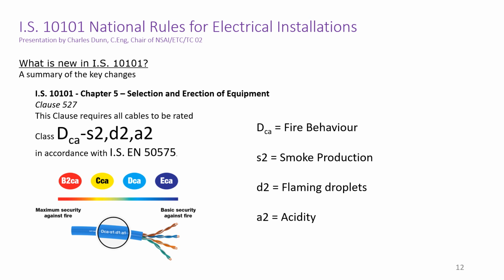European standard EN 50575 now defines the fire rating of cables based on several characteristics. The first letters, DCA, refer to the flame propagation and heat emission test of a cable. This is standard stuff we've seen over the years for cable ratings. How long will a cable withstand a fire and of what intensity? The second part, S2, refers to the rate of emission of smoke and transmittance of a cable. This defines the amount of smoke the cable will emit and how obscuring the smoke will be.